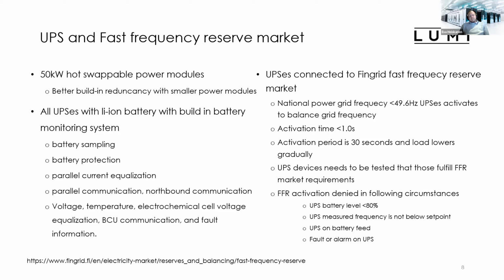These UPS devices need to be tested annually to verify that they fulfill the fast frequency reserve market requirements. So we do this test every fall when this market ends. This market is currently activated only during the summertime, and this is a pretty new reserve market. It was implemented in the Nordics in May 2020, and Fingrid procures the reserve from a national market in Finland.